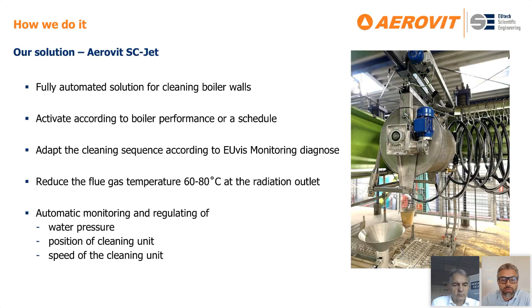But also, if you implement it in a new boiler, you will have a minimum number of inlets in the boiler roof due to the range of the water jets from the SC jet nozzle head. It sprays the water more than 5 meters in each direction. And again, it's the droplets. When it hits the surface, it expands into vapor. This expansion is about 1,700 times when it goes from liquid to vapor, and it's this explosion that rips off the fouling on the membrane walls.